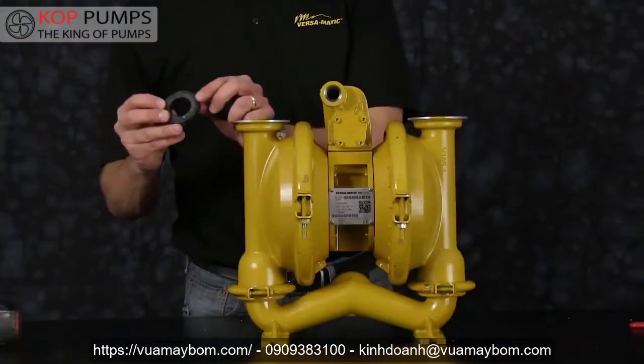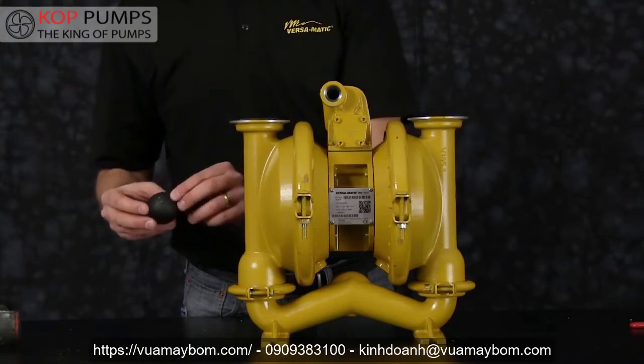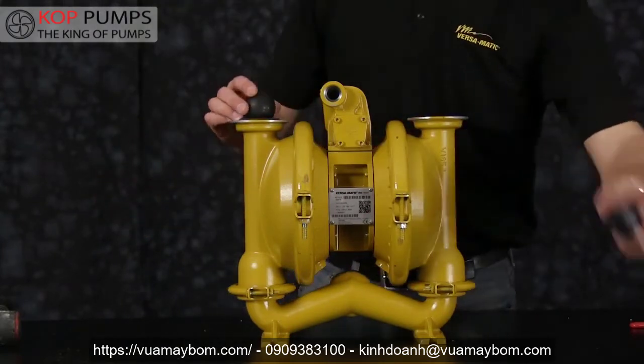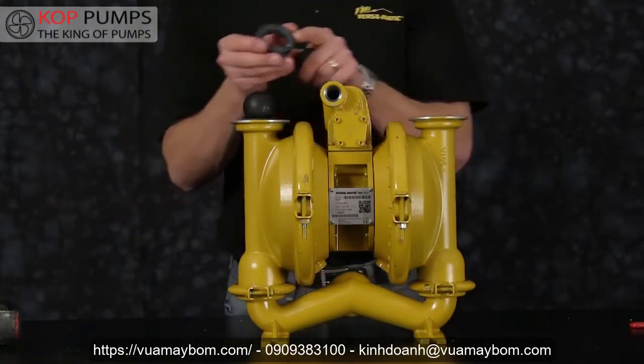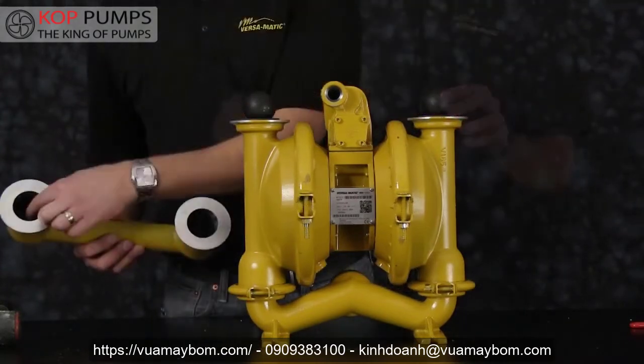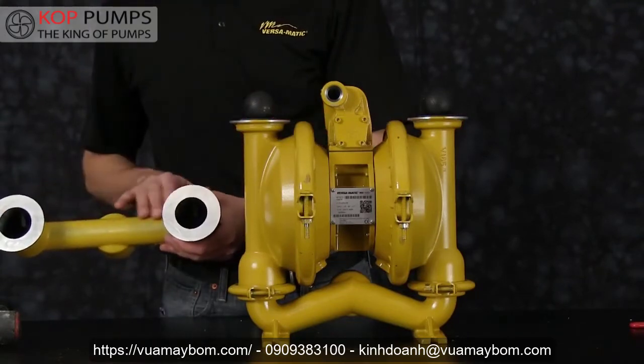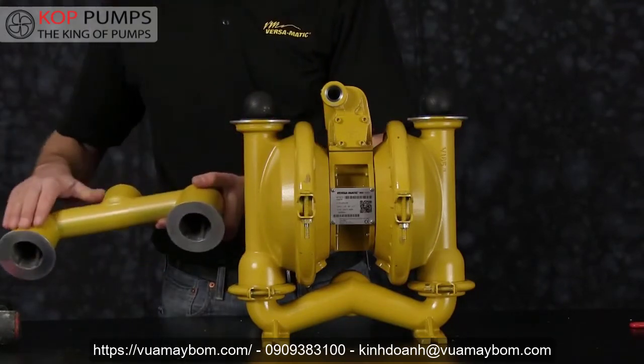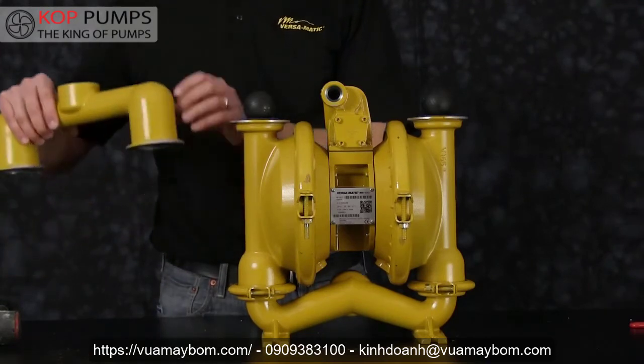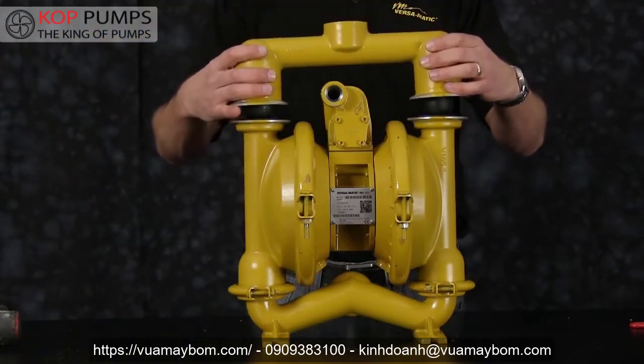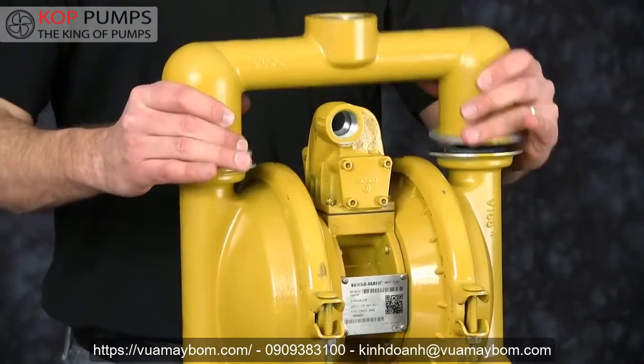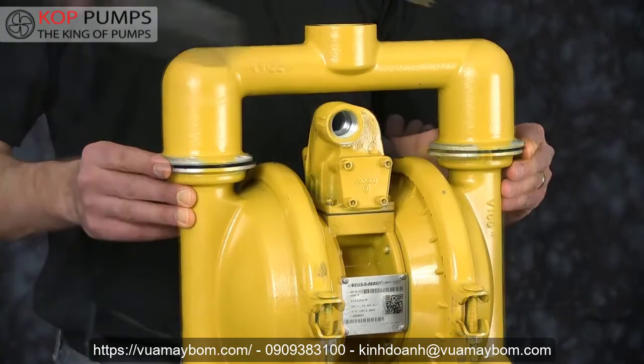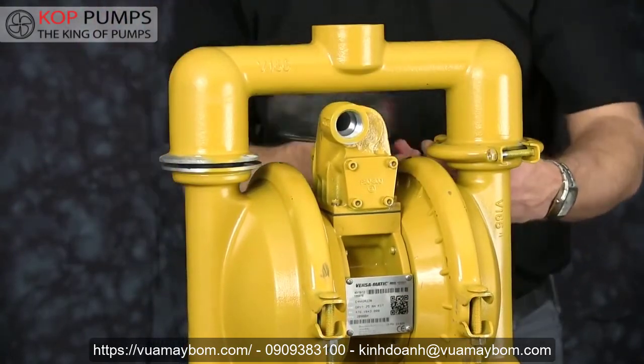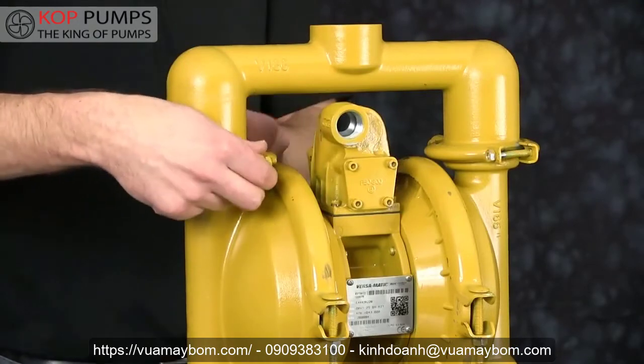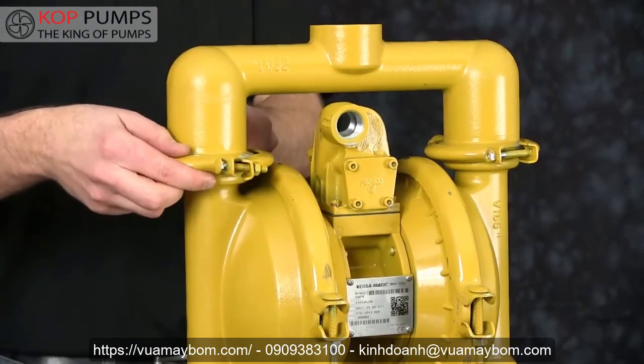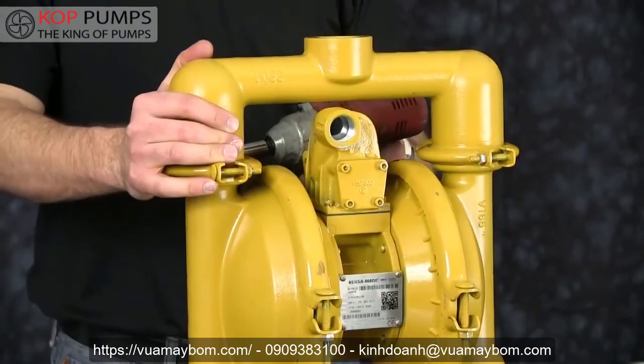Now we're ready to install our discharge valve seats and check balls. Note the orientation of the valve seat. The O-ring of the check valve seat will face down and the flat surface of the check valve seat will go towards the ball. Inspect the integrity of the casting of our discharge manifold. Inspect the machine surfaces and the ball guides for any sharp edges and address those sharp edges if need be with a light sandpaper or crocus cloth or emery cloth. If too far gone or worn, replace as needed. Now install our clamp band assemblies over top of the outer chamber flange and discharge flange. Again, there's no torque spec for the clamp band assembly, but to tighten evenly.